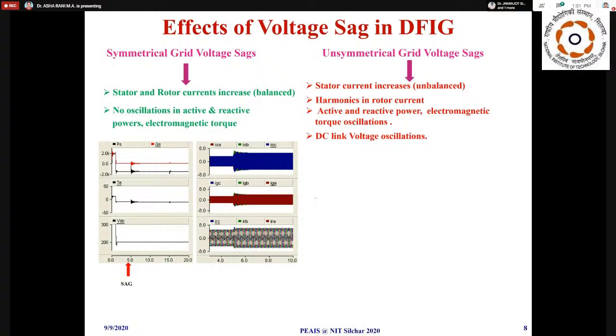Why I am saying this is, let us say I want to pump a power of 1 megawatt to the grid. Whatever you are pumping, the terminal voltage is nothing but the line voltage, that is 400 volts. So 1 megawatt divided by 400 gives some current, right? If you have a symmetrical grid voltage sag, the meaning is that earlier I had 400 volts, and now the voltage, let us assume, is reduced to 390. So what happens? Power divided by this reduced voltage, your current will be more.